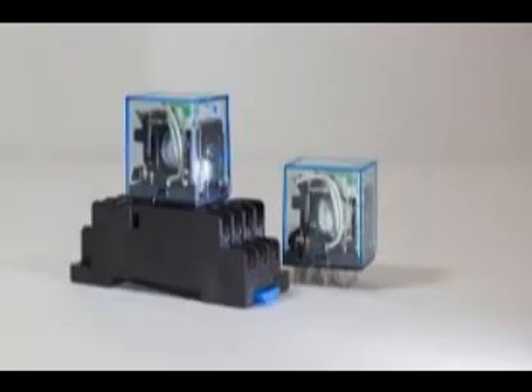Simple but effective. Now, the document talks about normally open and normally closed contacts. What do those terms actually mean in practice? Good question. This refers to the state of the contacts when the relay coil is de-energized, when the relay is just sitting there, turned off. The default state. Exactly. Normally open, or NO contacts, sometimes called make contacts, are open in this state. No connection. When you energize the coil and the relay switches on, these contacts close. They make the connection, completing the circuit.